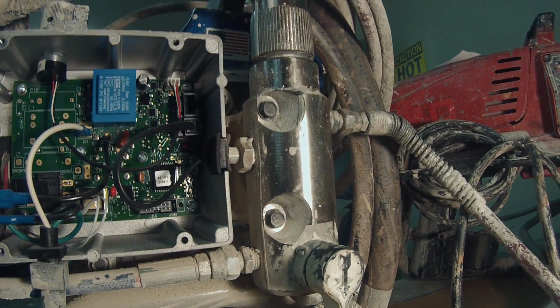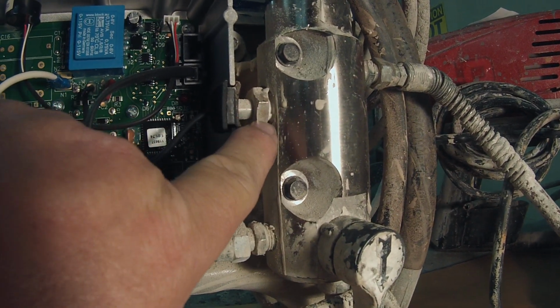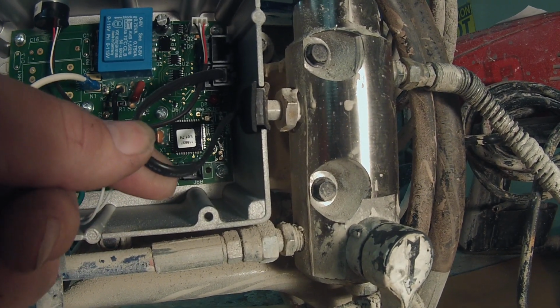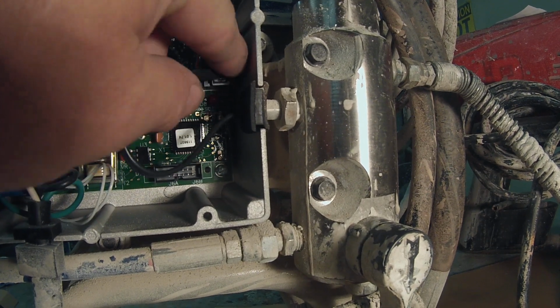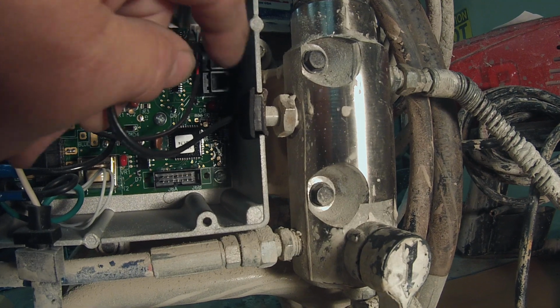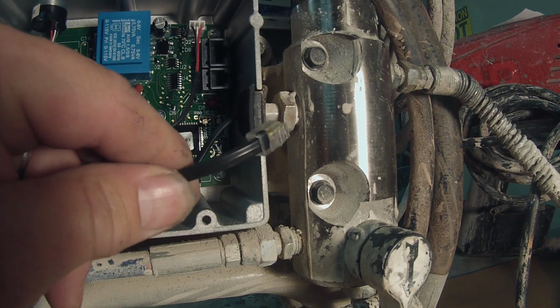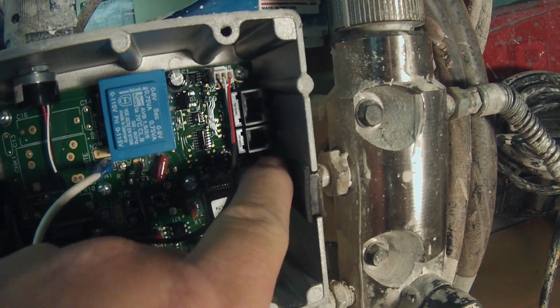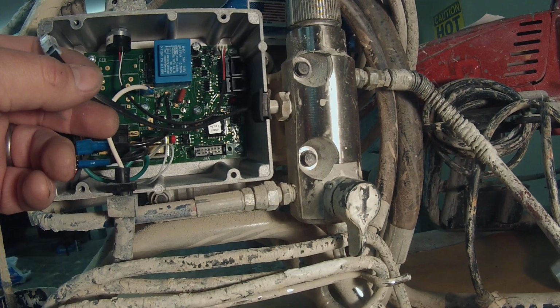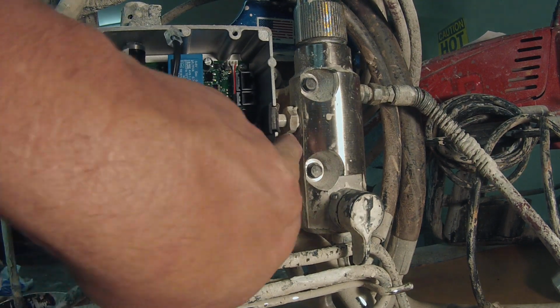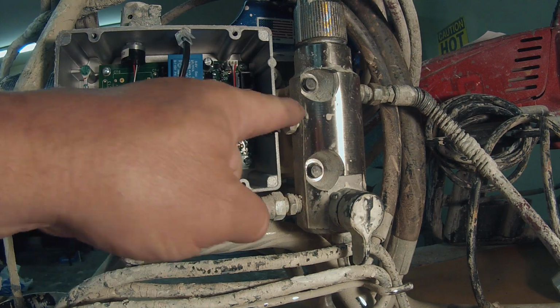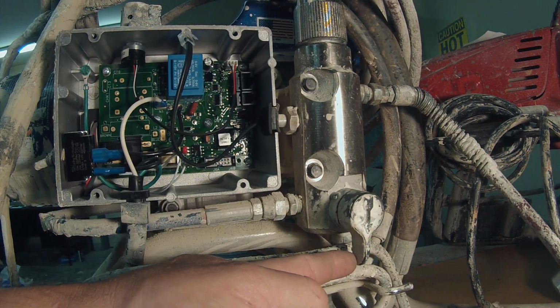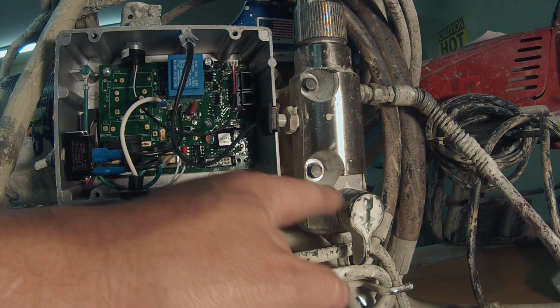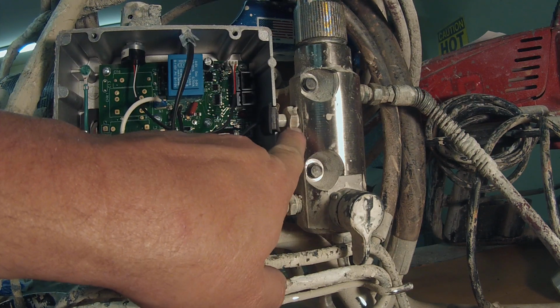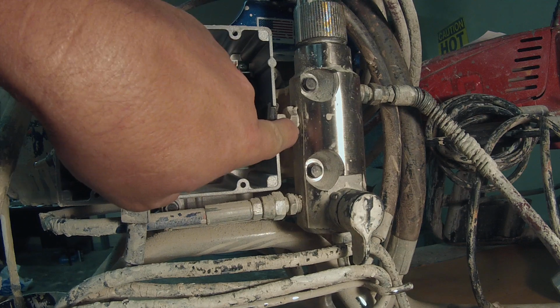So the transducer itself again is right here. It's this item here. This is the wire, and for some of you older guys, you may remember your landlines, when they plug in, the wire looks like this, and all you do is press the tab and pull out of that port right there. Once you've got it unplugged, you're ready to actually remove the transducer. You're going to take a 3/4 inch wrench, you're going to slide it on here, and you're going to loosen that item there. Now make sure your pressure is off so we don't have a leak here. The machine is unplugged again. So you'll take your 3/4 inch wrench, you'll loosen this item here, that collar will slide back.